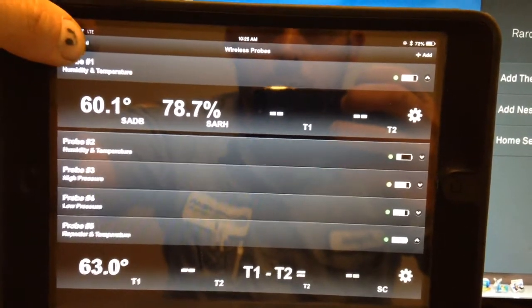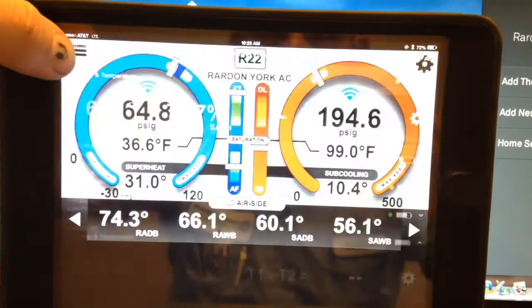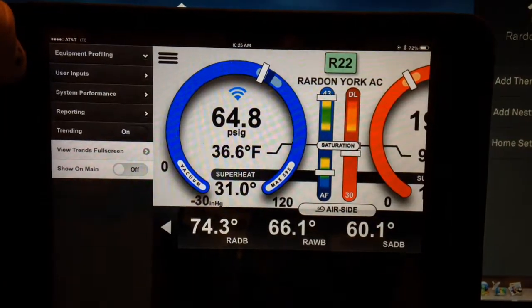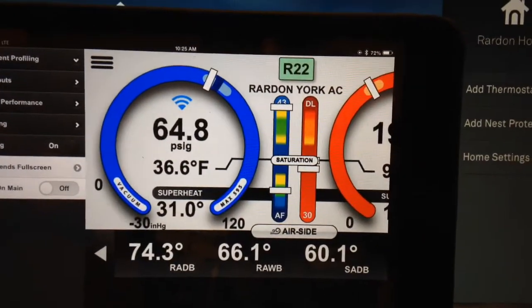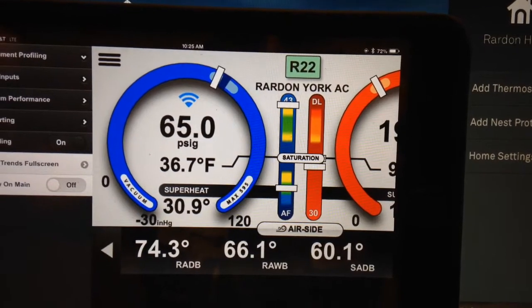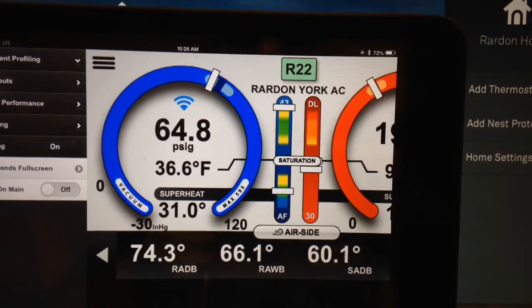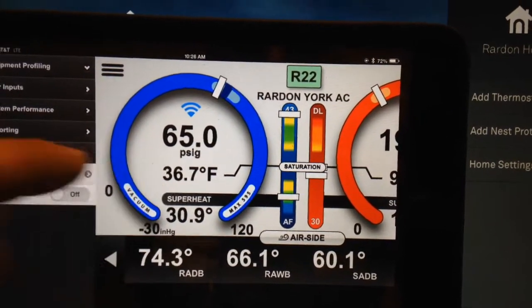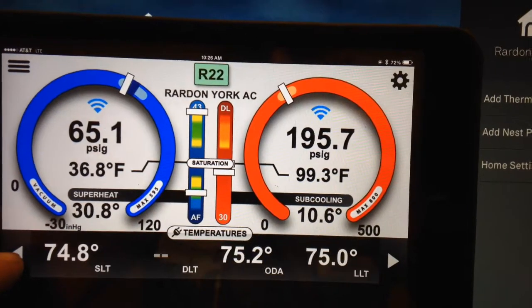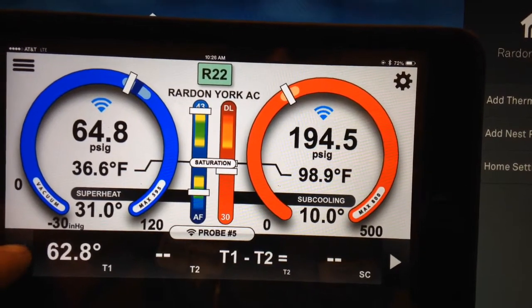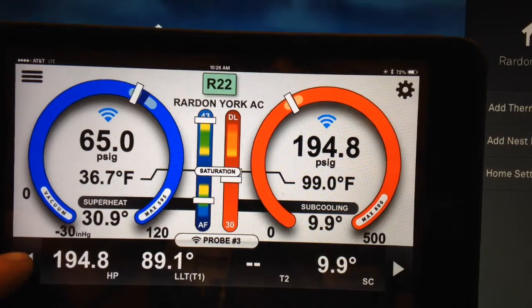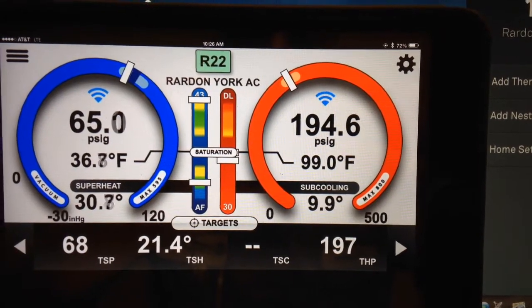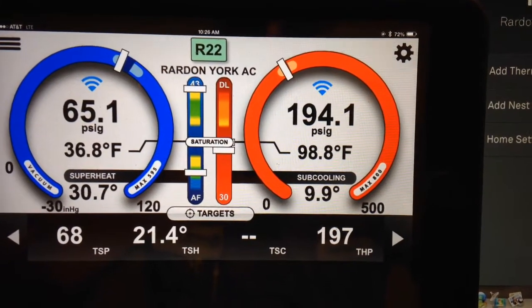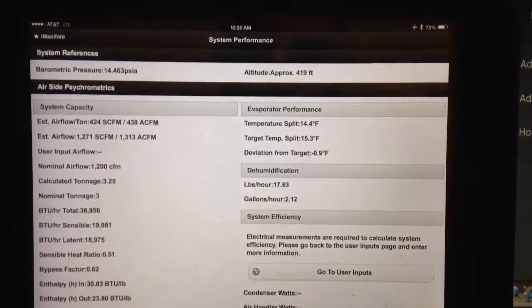Just so that we cover as much information as possible, we're going to go ahead and go over to system performance. You can see that my pressures are within the allowable range. Superheat is probably off, and let's actually go look at that for a second here. We're going to look at target superheat. My pressure is pretty close, but my superheat is obviously off by about 9 degrees. And there you have it.